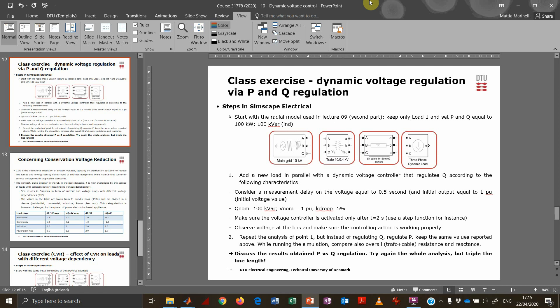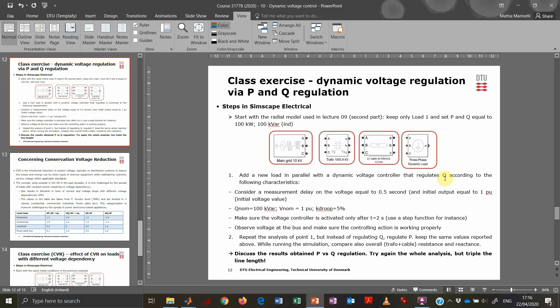Let's go through the last couple of exercises in the course. We want to discuss how to implement a dynamic voltage controller - a classic droop controller - to adjust either active or reactive power in order to raise the voltage in our distribution system. The grid we are using is the usual one: main grid, transformer, cable, and controllable load. We start from the same conditions as the previous example: 100 kW and 100 kVAr as initial load. We want to add a new load in parallel with the possibility of adjusting reactive power first, so we need to add the load and design a controller.